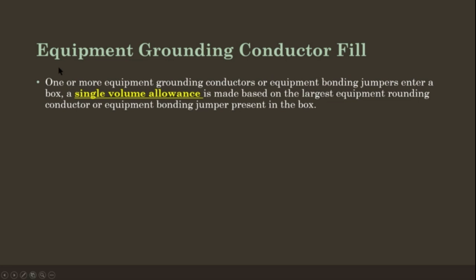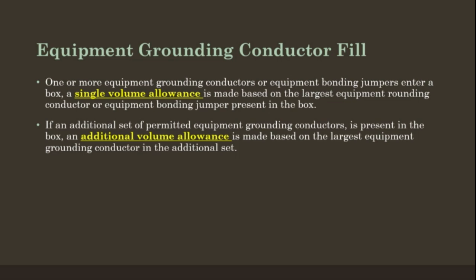Equipment Grounding Conductor Fill. One or more equipment grounding conductors or equipment bonding jumpers enter a box. If an additional set of permitted equipment grounding conductors is present in the box, an additional volume allowance is made based on the largest equipment grounding conductor in the additional set.